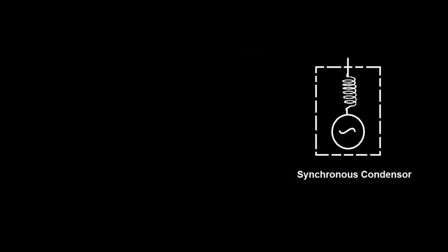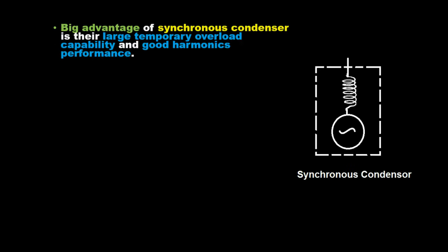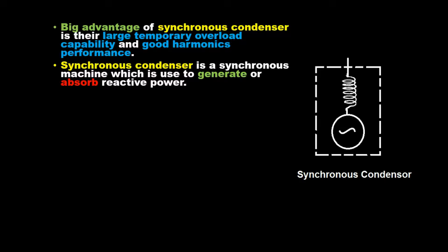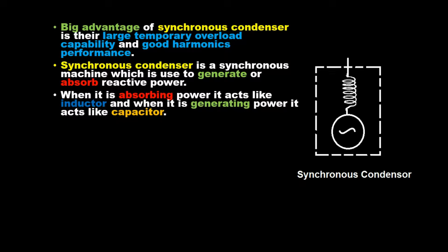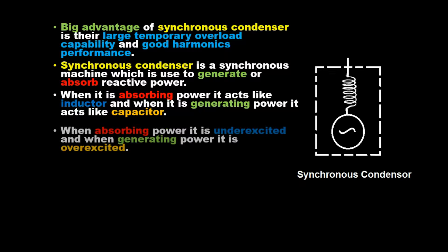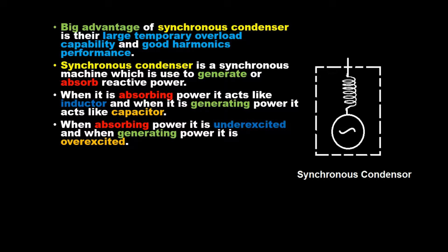A big advantage of the Synchronous Condenser is its large temporary overload capability and good harmonics performance. A Synchronous Condenser is a synchronous machine used to generate or absorb reactive power. When absorbing power it acts like an inductor and is underexcited; when generating power it acts like a capacitor and is overexcited.